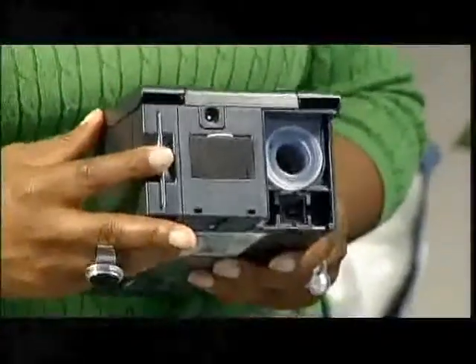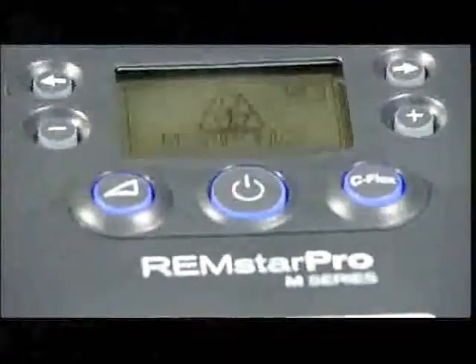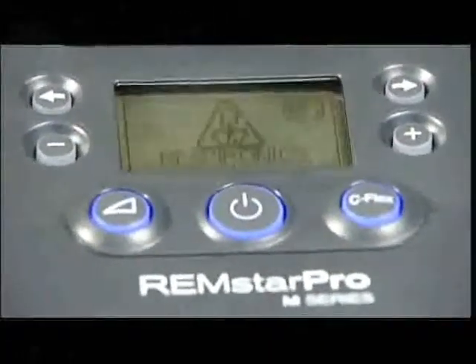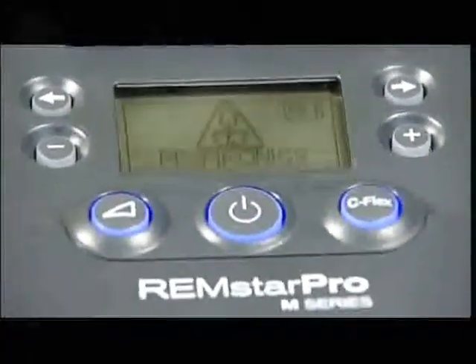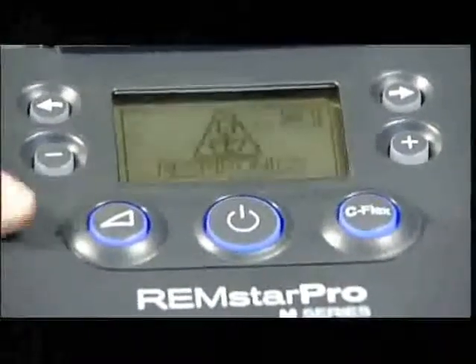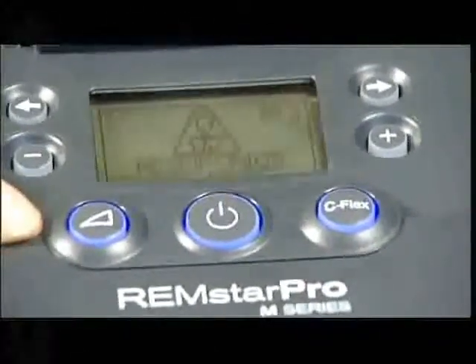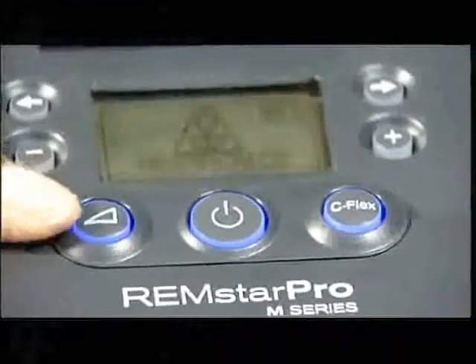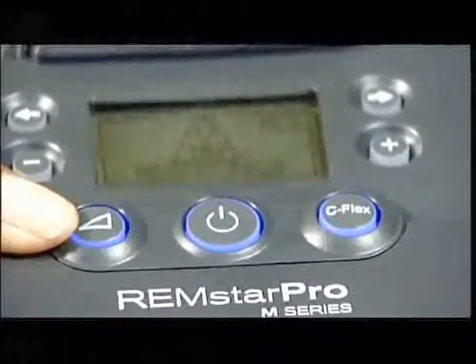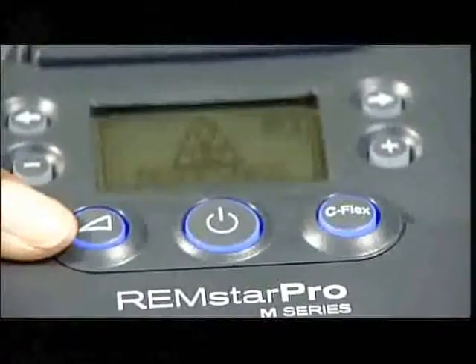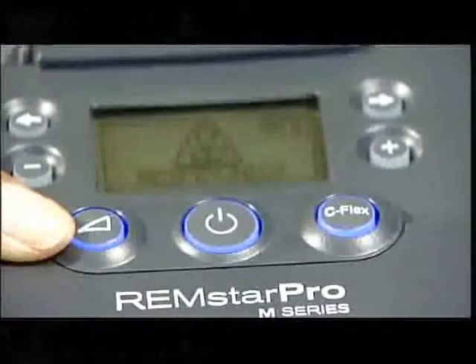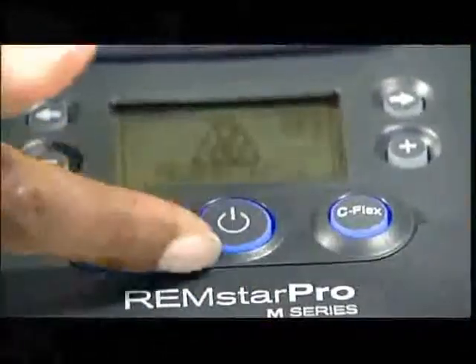On the front of your CPAP unit, lifting up this flap here will take you to your display window. Beneath the display window, there are 3 buttons, and these are your comfort features. The first being the ramp. When you press the ramp button, it drops the pressure to 4 from your set prescribed pressure. Use this button as your relief as you are adjusting to wearing your CPAP unit, and it gives you time to fall asleep.